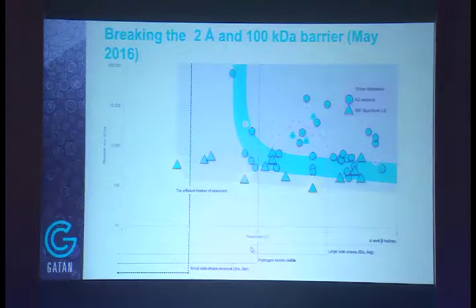Okay. And so I just wanted to show this one more time. We think that the energy filter certainly doesn't hurt the resolution, and there's a chance that when the Sriram group is trying to get these structures that are pushing the envelope, they're scraping for every percent improvement that they can get. And so they're using lower dose rates, and they're using close to focus images. So we think that it's probably a small but not insignificant improvement in the contrast of the particles that could be coming from the filter.